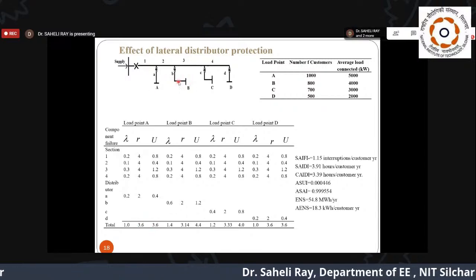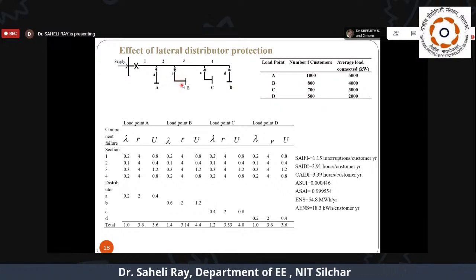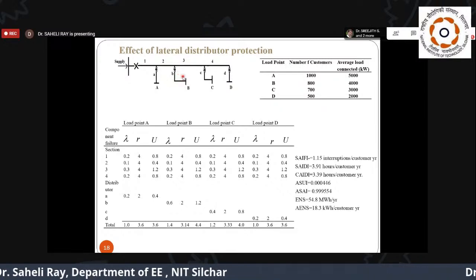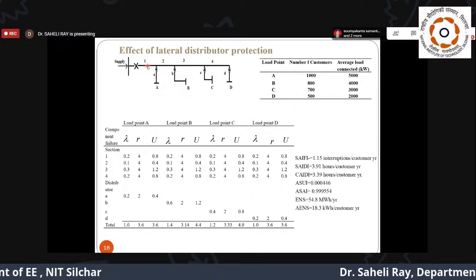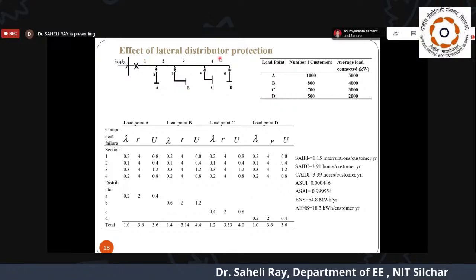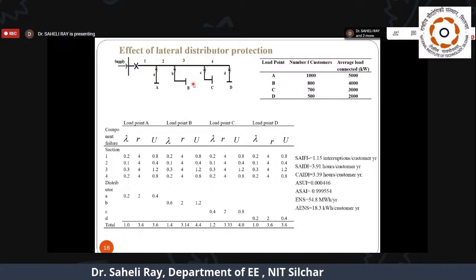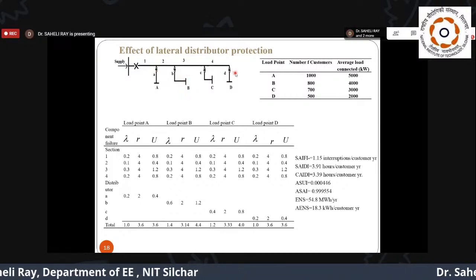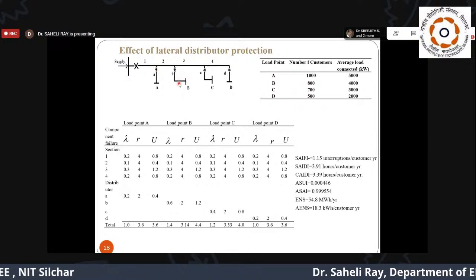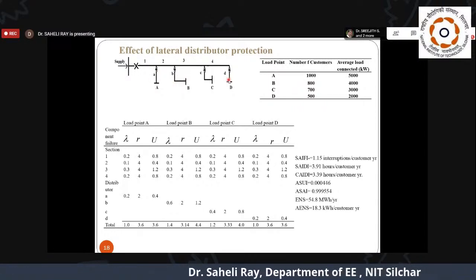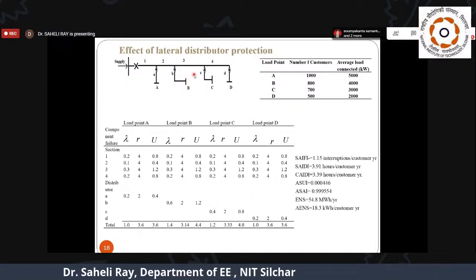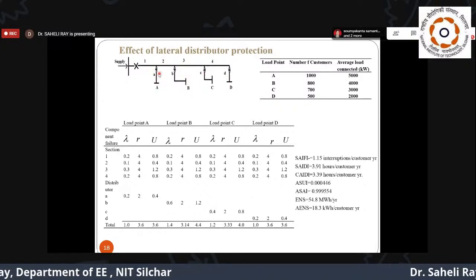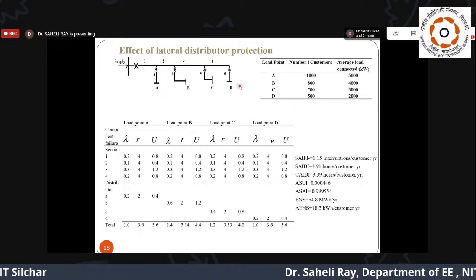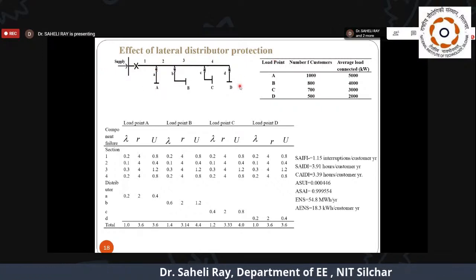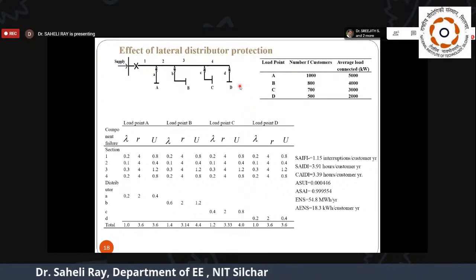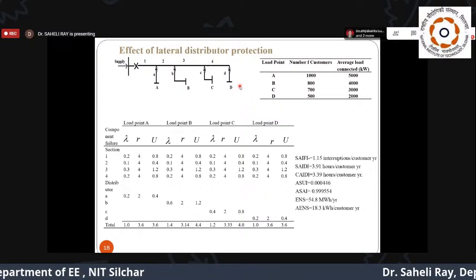Similarly, if we come to load point B, what will happen? If any fault occurs in main line segment 1, 2, 3, or 4, load point B will be affected. But for the lateral distributors other than B, a fault in any other portion will not affect load point B, because the fuse will blow and disconnect the faulty portion from the remaining healthy portion, leaving the healthy portion unaffected.